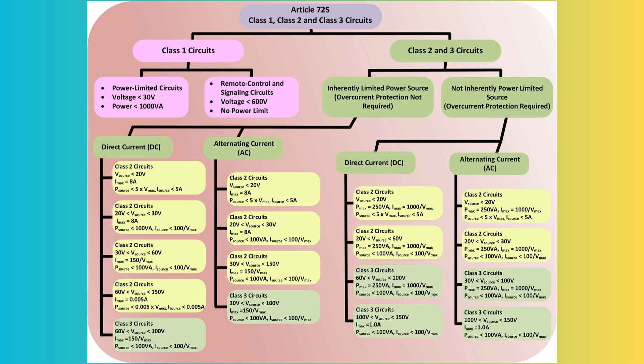Article 725 of the Electrical Code specifically addresses low-power circuits that are not an integral part of a device or appliance. These circuits, including those used for burglar alarms, access control, sound systems, nurse call systems, intercoms, low-voltage industrial controls, lighting dimmer controls, and certain computer networks, are categorized under Article 725. The primary goal of Article 725 is to establish specific conditions that allow low-power circuits to be distinguished from electric light and power circuits based on their usage and power limitations.